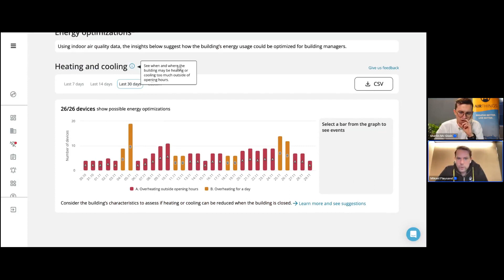This is slightly more advanced: it looks at the opening hours and the temperature, and also compares against the outdoor temperature. This then triggers an event saying we think you're heating too much, typically at night or on weekends.